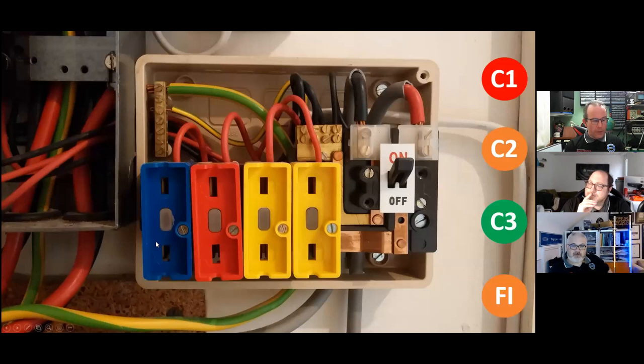Yeah, Chris Ruddock's put there, fixed load, no risk of overload, which is correct for that 30-amp one, the red one, because they had one storage heater on each. So although that is a single conductor, and it's a 30-amp fuse, which is obviously not correct in terms of overload, a storage heater isn't going to overload that single conductor. So that's an interesting one.